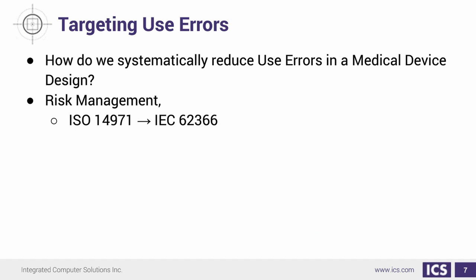So how do we systematically reduce use errors in medical device design? It goes back to ISO 14971, the risk management standard, but now largely applied in IEC 62366—the same process, just applied to the user interface. That's the method for targeting use errors.